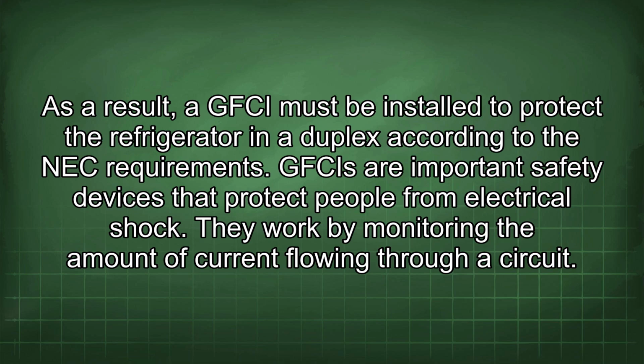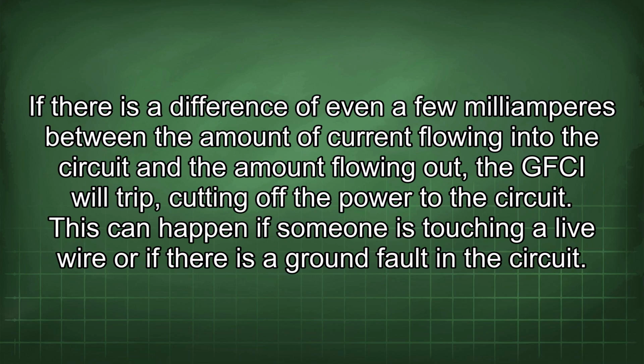GFCIs are important safety devices that protect people from electrical shock. They work by monitoring the amount of current flowing through a circuit. If there is a difference of even a few milliamperes between the amount of current flowing into the circuit and the amount flowing out, the GFCI will trip, cutting off the power to the circuit. This can happen if someone is touching a live wire or if there is a ground fault in the circuit.